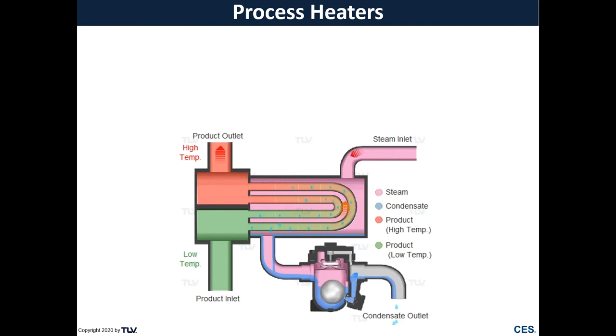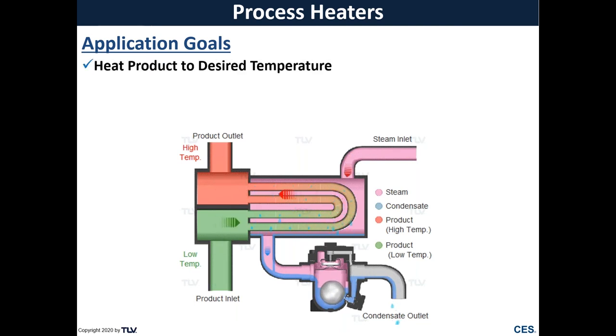All right, now we'll move into process heaters, which can be very broad. There's many different types of process heaters, but we'll take a look at a common shell and tube type heat exchanger, where we're taking cold product in the bottom in green, we're heating it with steam on the other side of that heat exchanger, and we're raising it up to a desired set temperature. So the application goals here are to heat a product up to a desired temperature. And we're going to want to vent air quickly out of this heat exchanger on startup, especially if this is a batch operation type heat exchanger. If we can vent air quicker, we can have a shorter batch time.